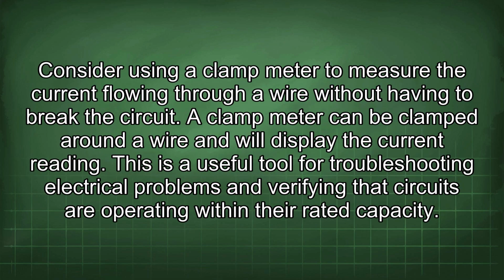Consider using a clamp meter to measure the current flowing through a wire without having to break the circuit. A clamp meter can be clamped around a wire and will display the current reading. This is a useful tool for troubleshooting electrical problems and verifying that circuits are operating within their rated capacity.